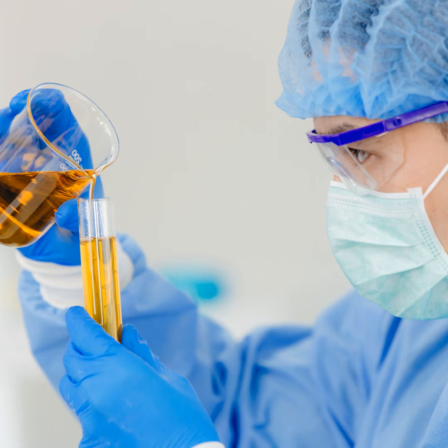So, what are the key lessons from today's episode? Firstly, hydraulic cleanliness isn't something that's estimated by eye. It's measured using recognized international standards that provide a consistent language for reporting contamination levels. Secondly, while several standards exist, ISO 4406 has become the most widely adopted because it's internationally recognized and straightforward to apply.